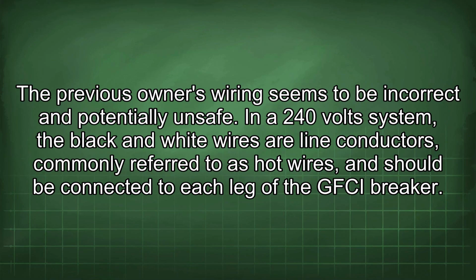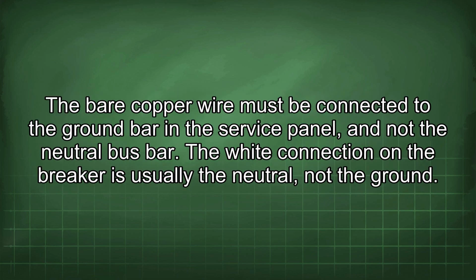The previous owner's wiring seems to be incorrect and potentially unsafe. In a 240-volt system, the black and white wires are line conductors, commonly referred to as hot wires, and should be connected to each leg of the GFCI breaker.